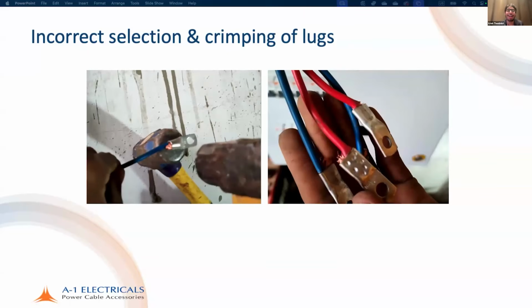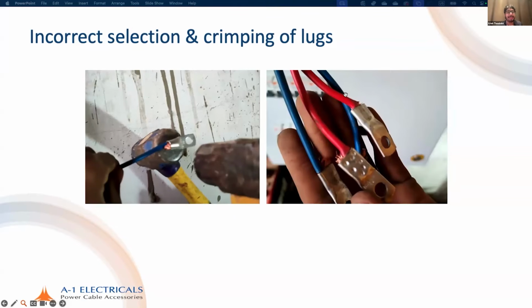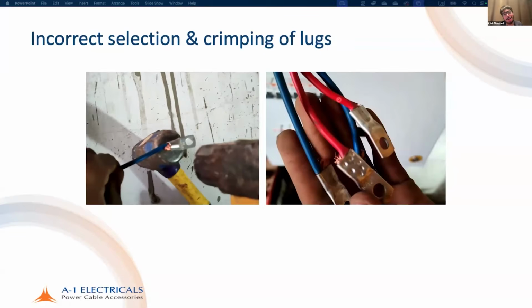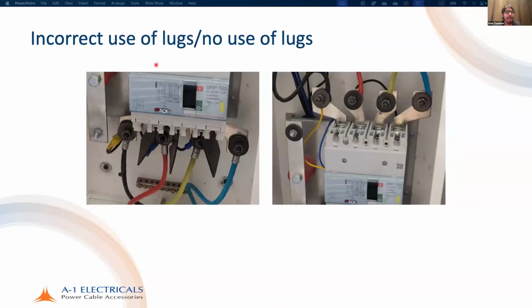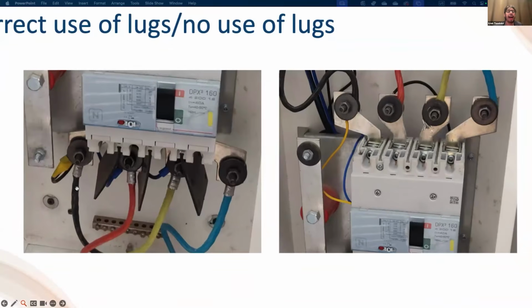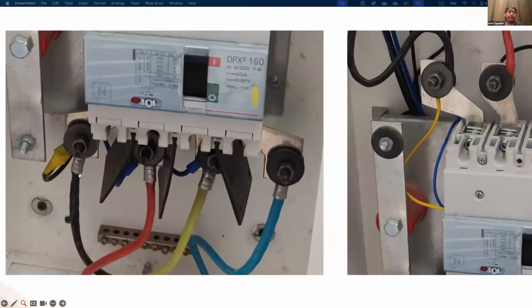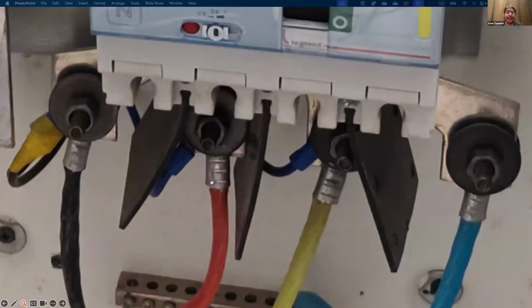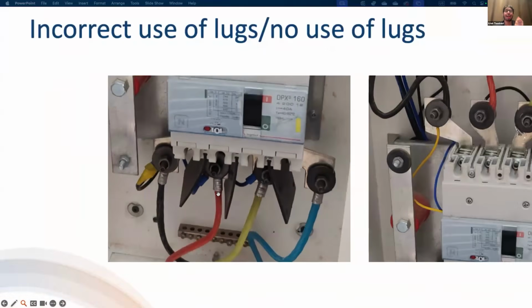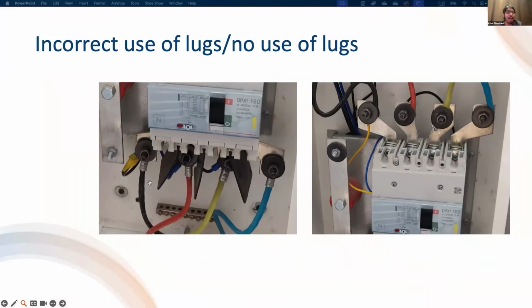So unfortunately, we are in a situation where we are not correctly selecting products, and in terms of crimping, we are not really using any correct tools. So buying a generic crimper is not really a good idea at all. Oftentimes, when there is no lug used, for example, they are just twisted around and there is a nut and a washer and it is held in place. And here we have, for example, a plier that has just applied force on this. You can see it's badly scratched up. It's not even crimped. And any little bit of force that you apply, it will just come off the lug. Of course, here you have double door. This is a particularly bad condition.